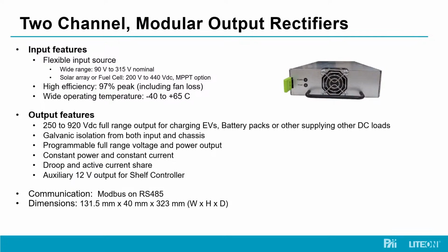These are a 3.3 kilowatt rectifier. We arrange these in a shelf to be 10 kilowatts, which I'll cover in a minute. These provide a wide range output, 250 to 920 volts DC, for charging electric vehicles, other battery packs, and generally providing power to other DC loads. Each one is galvanically isolated from the input and the chassis, and can provide constant power and constant current, particularly needed in EV charging applications.